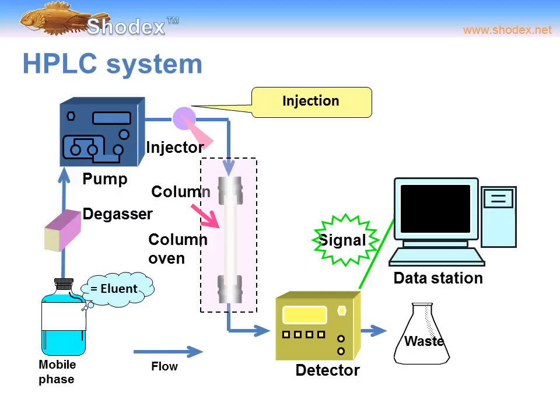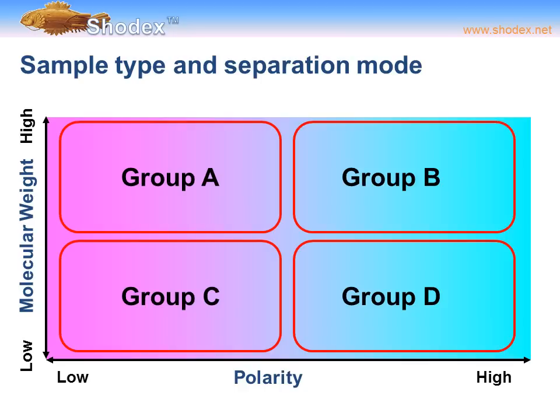After the pump, the eluent moves past the injector port and into the column, then into a detector where a signal is taken and then into the waste stream. The analytes themselves are injected at the injector port. The eluent carries the analytes into the column, and based on physical, chemical, or both types of interactions between the stationary phase, the analytes, and the mobile phase, the analytes are separated as they move through the column. Afterwards, the signal is taken from the detector and moved into a data station where the analyst can identify the analytes.